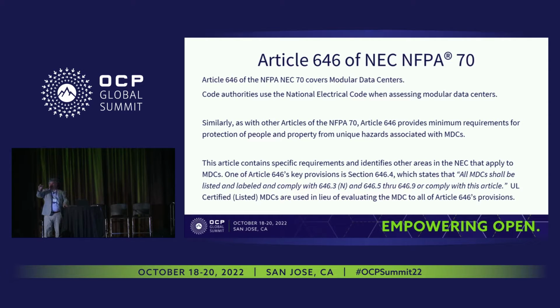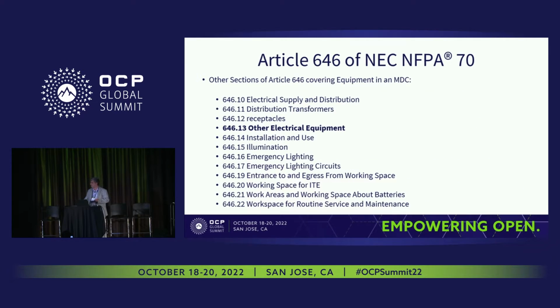So just to take it off the board, your MDC does not have to be listed by any NRTL as long as you comply with all of those articles. So it doesn't have to be listed, but the path to compliance is a lot harder if it's not.